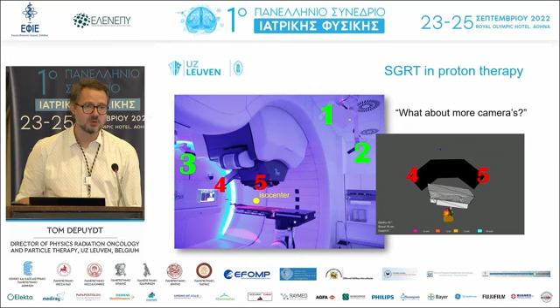And then we did a study where we virtually added these 2 cameras to have a 5-camera system that is more optimized for that environment. And then we made treatment plans that were optimized, which means that for each field in proton therapy, we optimized the air gap, made it as small as possible, but still allowing SGRT to be used for patient setup and monitoring. We did that for the 5-camera system and for the 3-camera system, the standard one. And then we compared with the standard methods where we basically reduce the air gap maximally to something like 7 centimeters, where you cannot use, or there's only limited use of SGRT, just to look at plan quality.